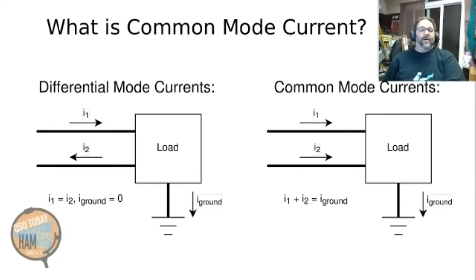Now, those common mode currents cause problems. You want the currents in your 2 different wires to be perfectly balanced. Anytime you have an imbalance in those currents, that causes problems, notably because Kirchhoff's current law tells us that current has to go somewhere. You can't magically have current going down a wire and then have it evaporate. It has to go somewhere, and where it goes is typically not where you want your power going. In the diagram I've shown here, the example is that it goes to ground, and that causes all kinds of problems.